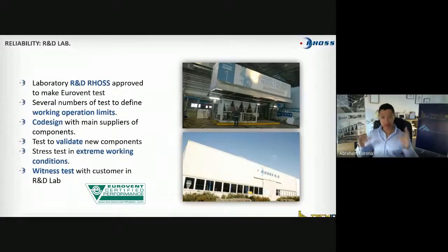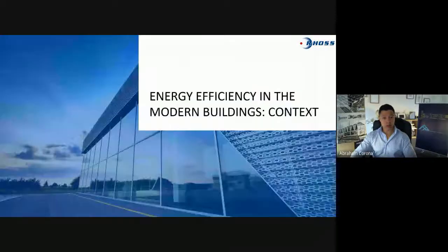What you see in the bottom is the entry to the lab. It's a different scenario. In this lab, we can simulate any environment condition between relative humidity and temperature up to 50 degrees. In other words, we can simulate any Australian condition even before the chiller leaves the factory. If we can program the test at the factory, what if you have an important project and you want to see the chiller already running there at any condition? We can simulate that, and you can actually go to Italy, have a good look at the machine that you have ordered from us.